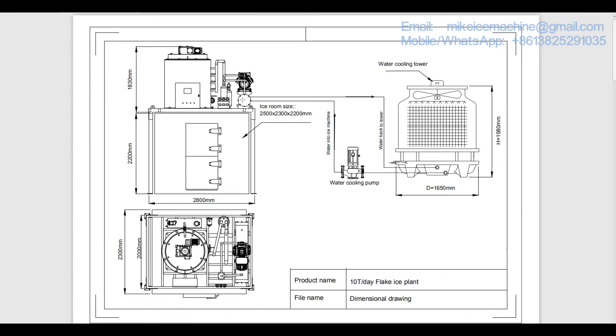This is the compressor, and this is the water cooling condenser. This is the water cooling tower, and this is the water cooling pump — the pump maintains the water circulation between the condenser and the cooling tower. Water goes into the condenser from one line and comes out the other. Heat is carried from the ice machine to the tower and released into the ambient.